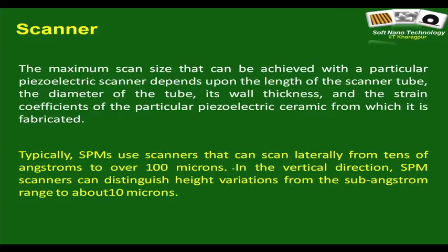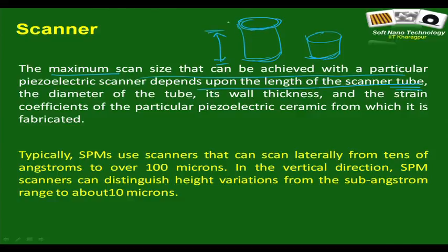There is also another important thing, that is the maximum scan size. The maximum scan size depends upon the length of the scanner tube. So if it is longer, the scan range is big. If it is shorter, the scan range is small.